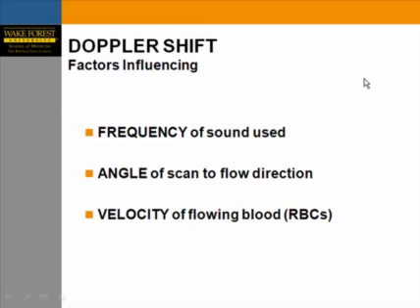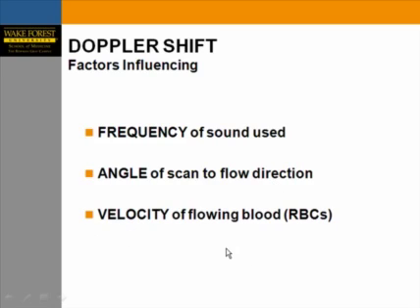The factors influencing Doppler shift are very important to consider while optimizing your color Doppler. The first is the frequency of sound used, the second is the angle of the scan, and the third is the velocity of flowing blood — the RBCs.